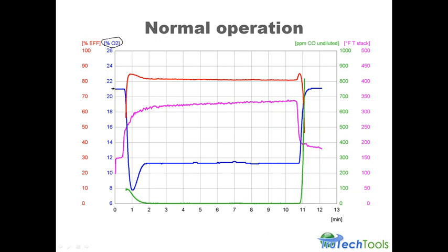Now here's the interesting thing here I want you to see. When the furnace first lit, it had excess gas that didn't get lit right away, and it lit with a little puff, you know, because all the burners don't light at once.